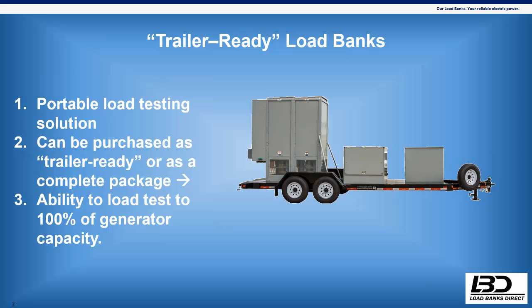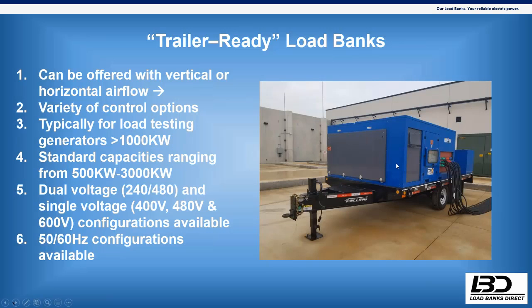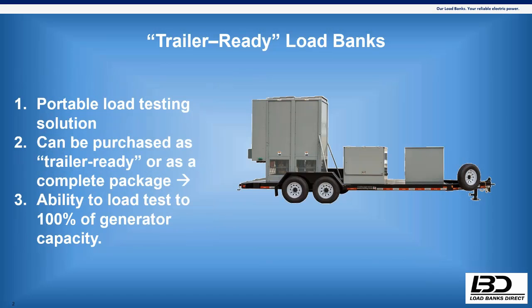In the stationary world, we definitely prefer vertical all day long over horizontal. But with horizontal, you get a lot more real estate and are able to do higher capacities at dual voltage—that's the main pro. Also, as I mentioned earlier, if you're load testing in a parking garage or similar space, you're never going to get one of these vertical load banks in there.